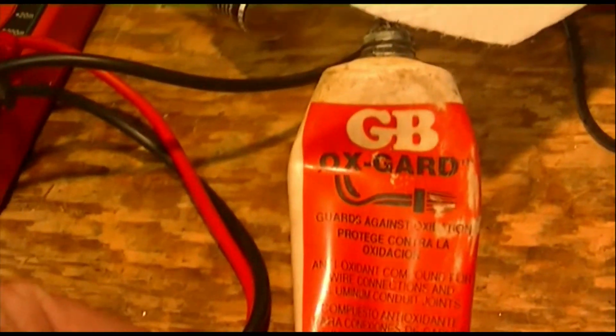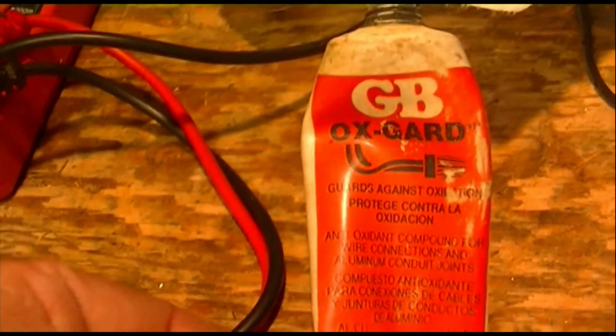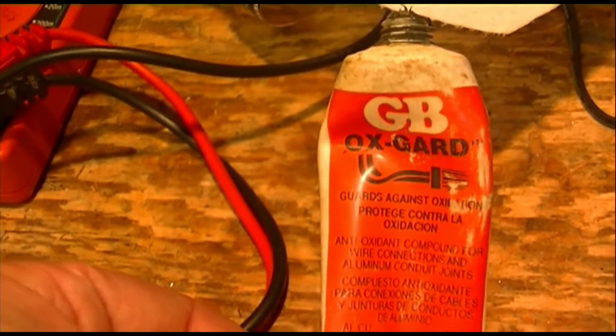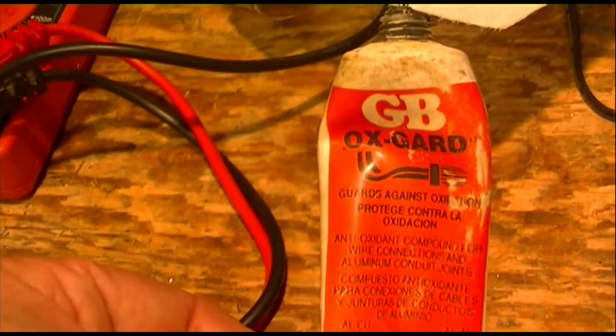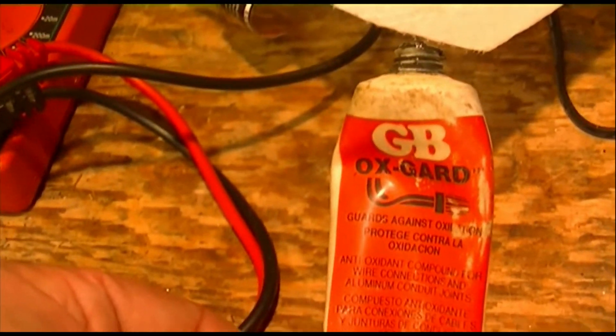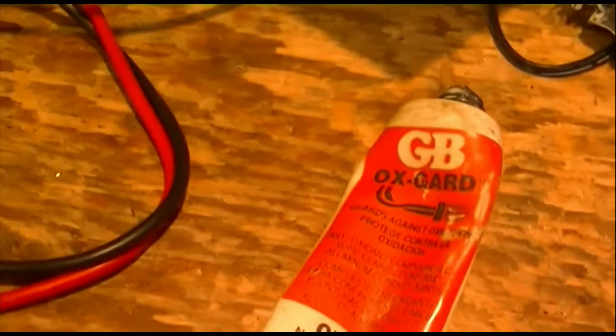Here you have some Gardner Bender Ox-Gard. This is a conductive anti-corrosive grease for aluminum connections and aluminum wires. You can buy this at any Ace Hardware store or Home Depot - go to the electrical section where they have circuit breakers and stuff, you'll find this. You'll probably also find Penetrox, which is another kind of antioxidant goop for these kinds of connections. It happens to be what Mosley sells.